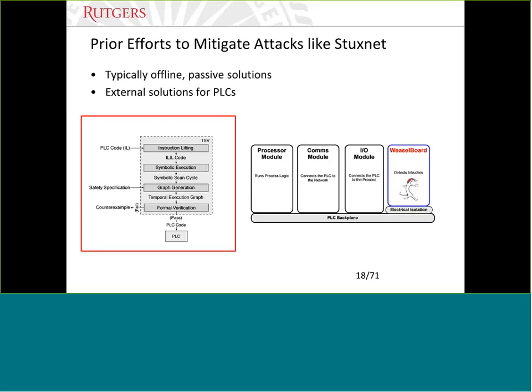The first case is TSV, the Trusted Safety Verifier, work done by our group. It acts as a verification mechanism, a bump in the wire between the PLC and the programming PC. The PLC code's instructions are lifted to an intermediate language, then symbolically executed and verified against safety specifications. This provides a way of formally verifying the PLC code loaded onto the PLC, but it's an offline solution since you can't do real-time monitoring of the code.